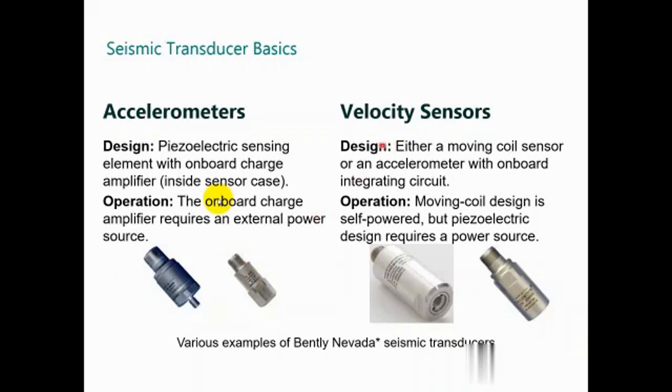The velocity sensor could be two types: the moving coil and the velometer. The velometer is a piezoelectric with an integrating circuit. The good thing for the moving coil is it's self-powered and doesn't require external power supply. The piezoelectric requires a power source.